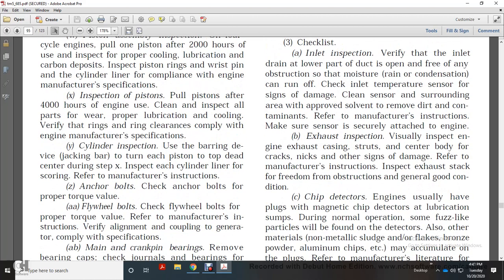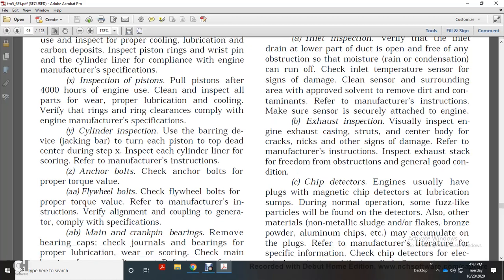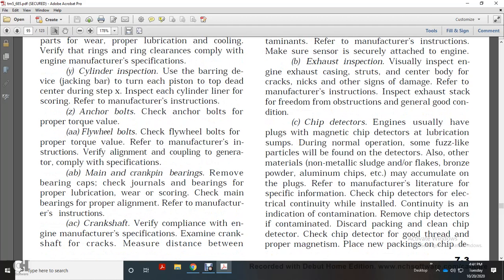Exhaust inspection: visually inspect the engine exhaust casing, struts, and center body for cracks, nicks, and other signs of damage. Refer to the manufacturer instruction. Inspect the exhaust stack for freedom of obstruction and general good condition. Chip detectors.